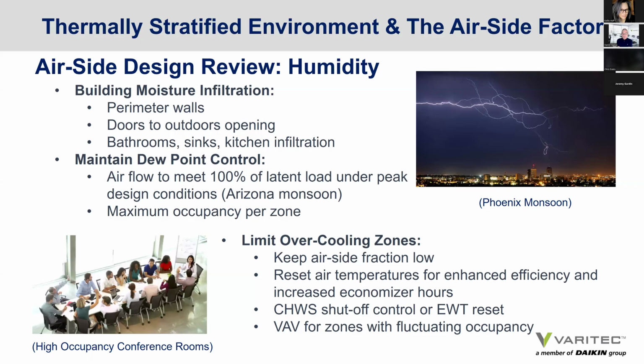So your biggest challenge is certainly in Arizona during our monsoon months, humidity infiltration from the perimeter. Outdoors, we're seeing dew points in the mid 60s, low 70s. I've seen it this last summer monsoon in August. So humidity control is very important in appropriately designing passive radiant cooling and heating designs.